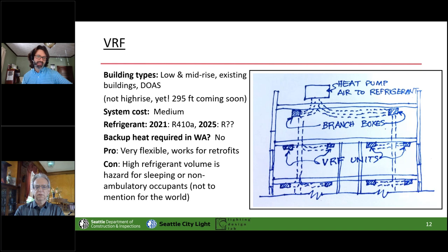But there's also R410A and the possibility that it displaces all the air. So if you do a really large VRF system in sleeping or non-ambulatory occupancies, you really got to look at that system volume. The standard for those taking notes is ASHRAE 15. And there's some caveats in there. But it comes down to if you've got enough refrigerant volume in a small enough space, you have a problem. The idea being that for some reason that pipe breaks in that apartment unit and dumps that whole loop worth of refrigerant into that apartment. It basically displaces your breathable air. Is that right, Ben? Correct.